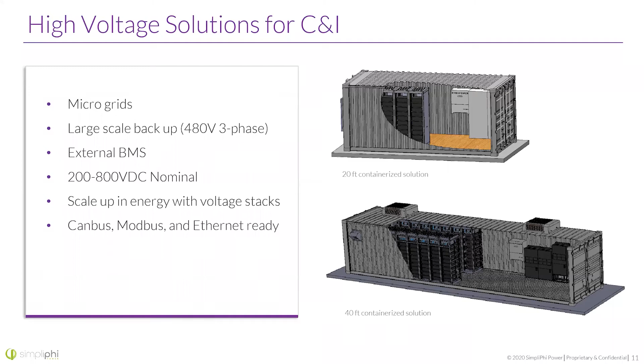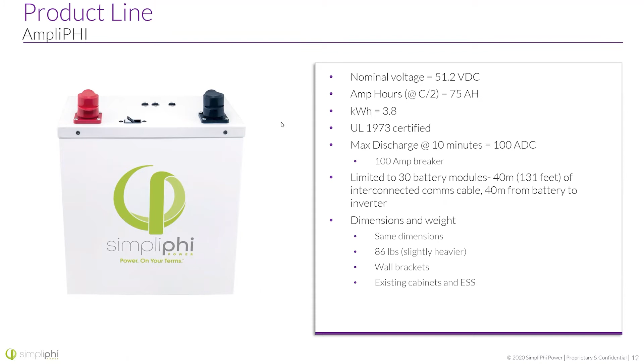Okay, awesome. We have our newest battery, the AmpliPHI battery. This battery is still a 3.8 kilowatt hour battery. The big difference with this battery is it has closed loop communication, so it's built to communicate with the inverter. Currently that's with the Sol-Ark inverter, and we're about to add some more onto that list shortly. It can do things like auto-populate set points, provide high-level protection, and it can actually read the state of charge, voltage, and charge and discharge. We'll talk about the AmpliPHI a bit more during this presentation. But this battery can report its own readings to give the inverter really high-level accurate readings, as well as be sized a bit more flexibly than our standard battery, as it tells the inverter how much to discharge.